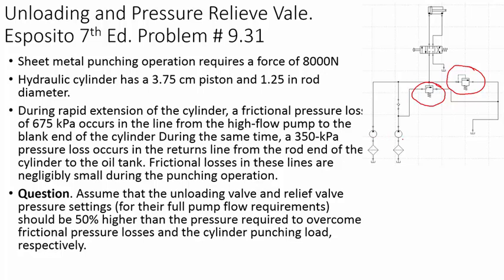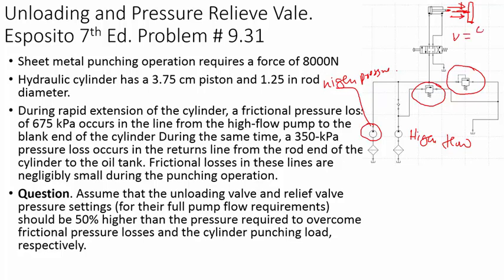The way these two pumps work: this pump is a high-flow pump, and this one is a high-pressure but low-flow pump. Two pumps are used because when this cylinder is extending — going very fast to punch the sheet metal — you need very high speed. To get high speed you need very high flow, since Q equals velocity times area.